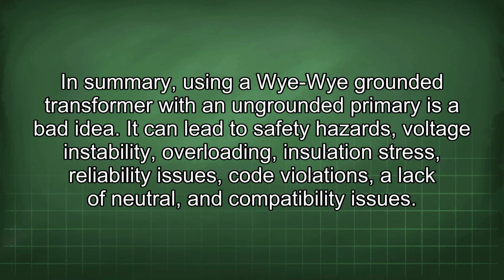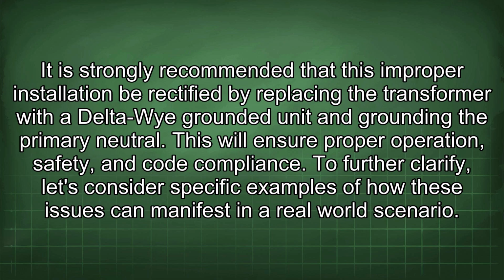In summary, using a Wye-Wye grounded transformer with an ungrounded primary is a bad idea. It can lead to safety hazards, voltage instability, overloading, insulation stress, reliability issues, code violations, a lack of neutral, and compatibility issues. It is strongly recommended that this improper installation be rectified by replacing the transformer with a Delta-Wye grounded unit and grounding the primary neutral. This will ensure proper operation, safety, and code compliance.